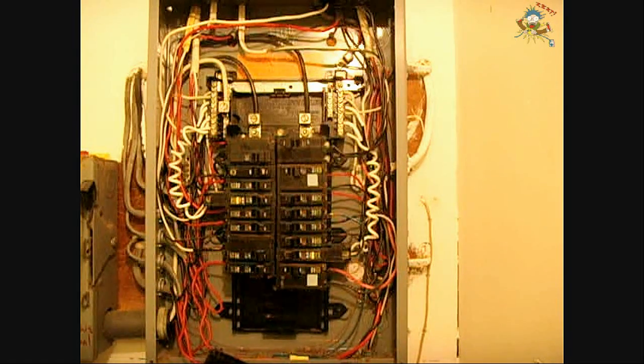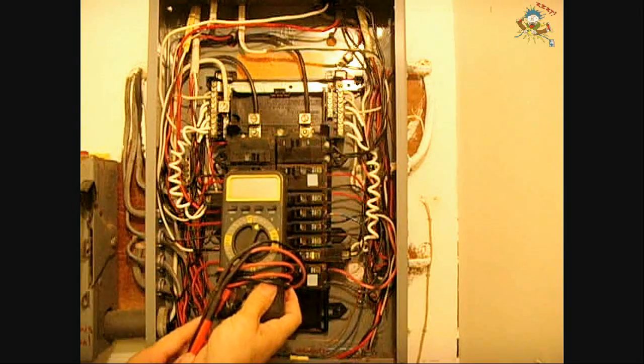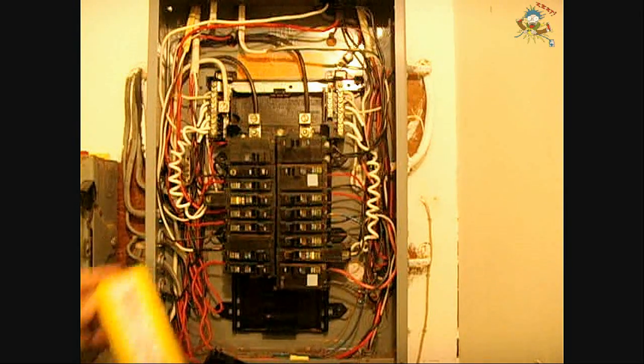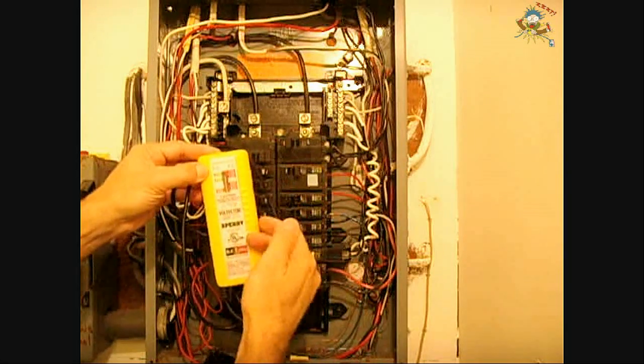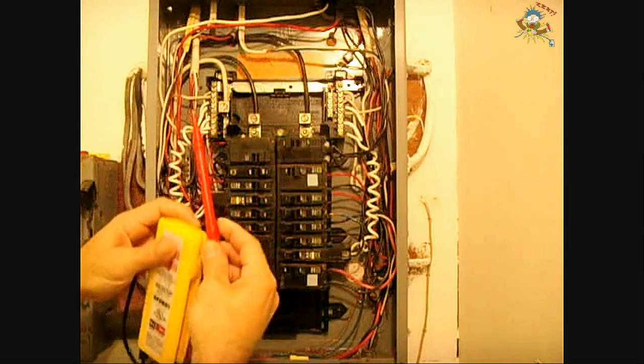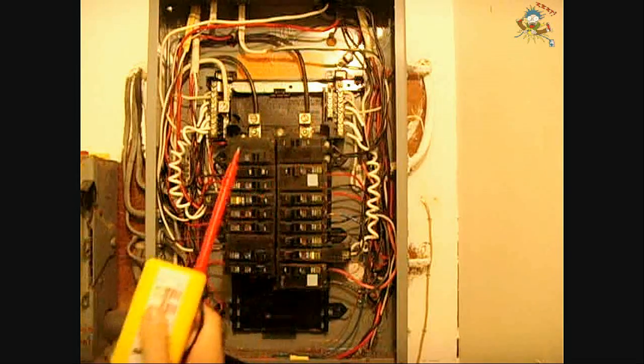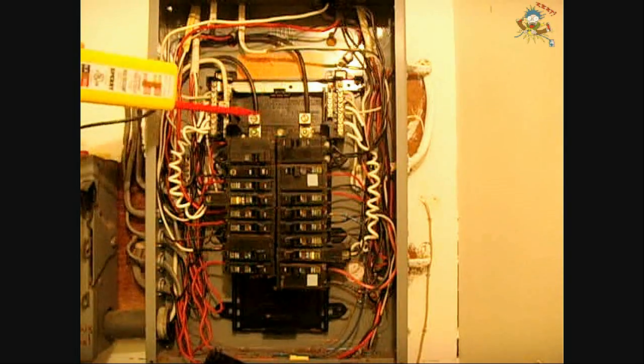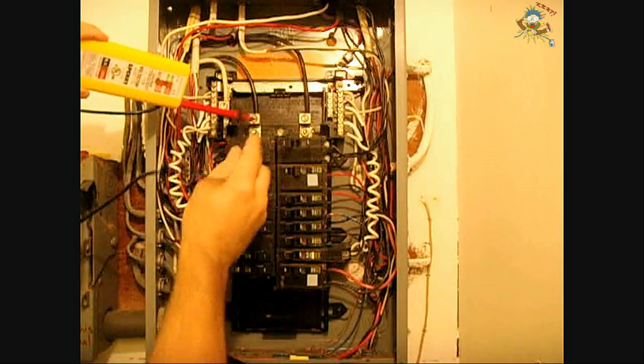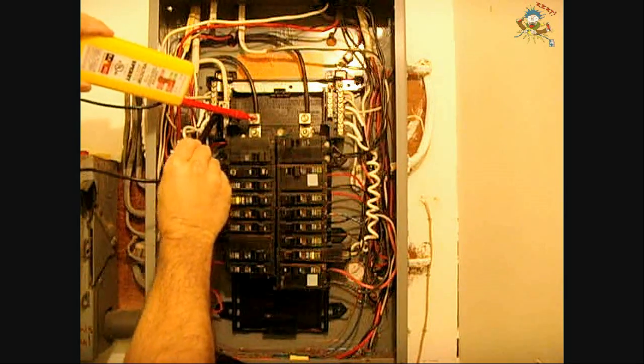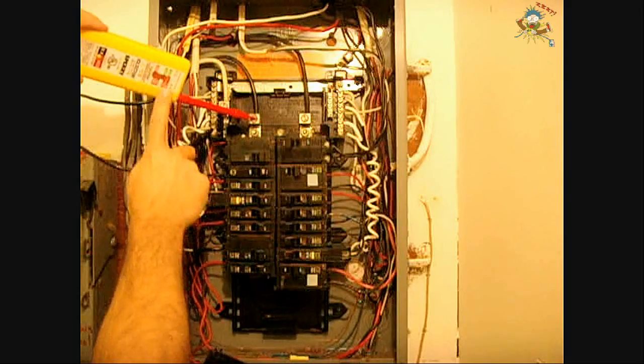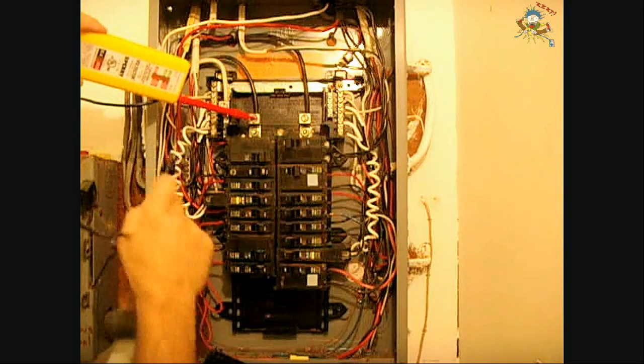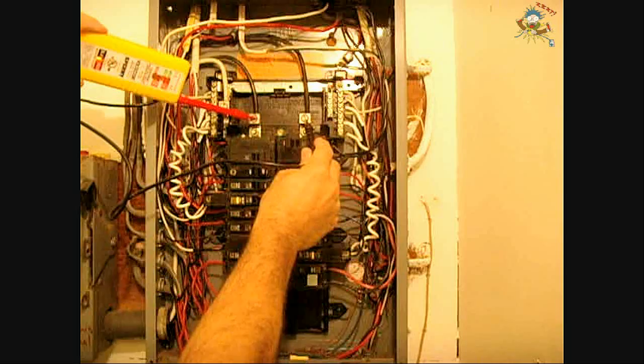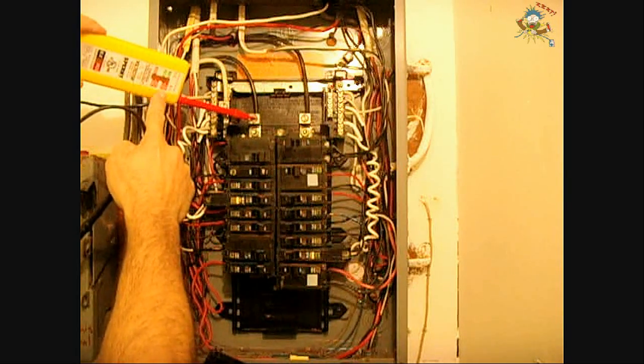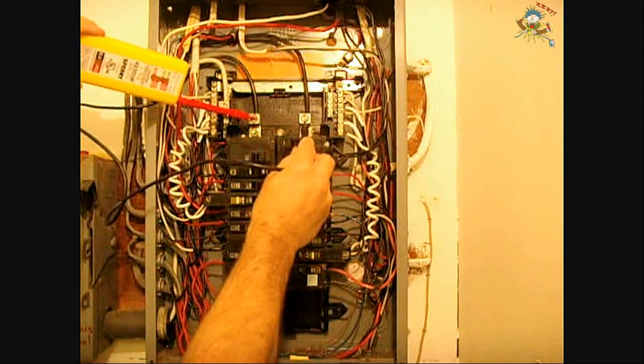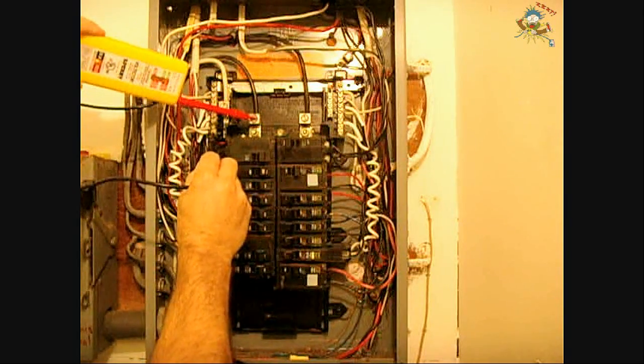Now, the tools you're going to want to use are a digital multimeter. You can also use a bar meter. This has a solenoid. When you take out the two connections, you can put them like this. Alright. The bar meter is very simple to use. Take one probe on one connection and you can go to ground. Alright, you can see 120 and the neon lamp glowing. You go to 240. It jumped over to 240. You saw the neon lamp is brighter, dimmer, brighter.